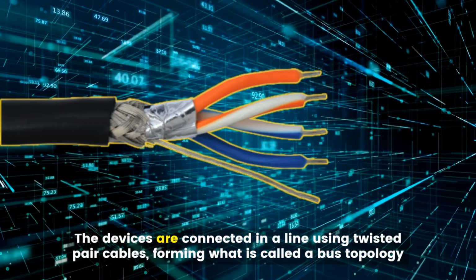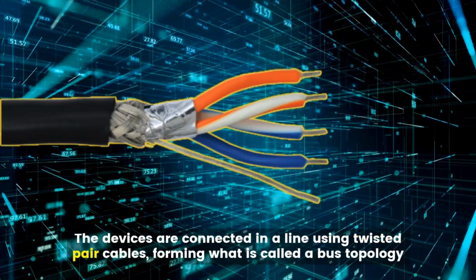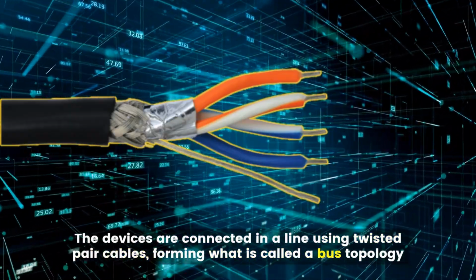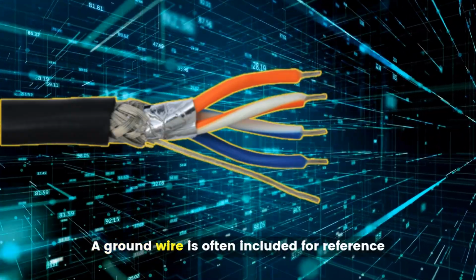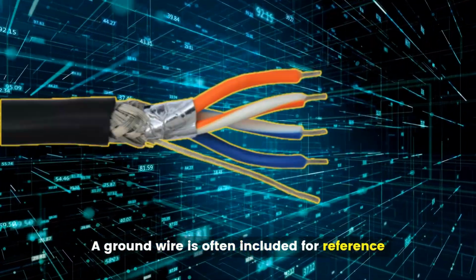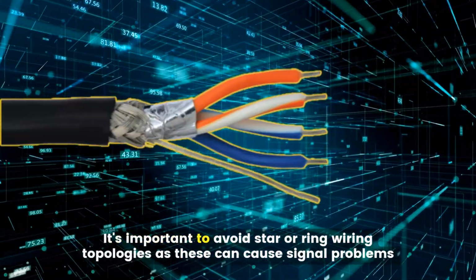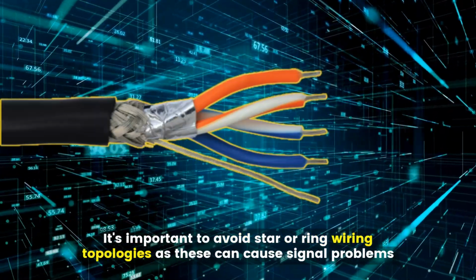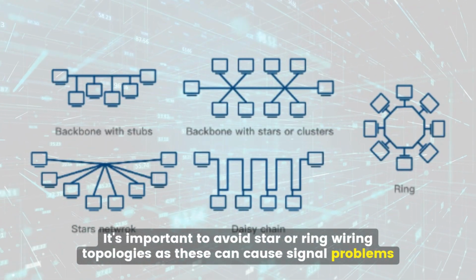The devices are connected in a line using twisted pair cables, forming what is called a bus topology. A ground wire is often included for reference. It's important to avoid star or ring wiring topologies, as these can cause signal problems.